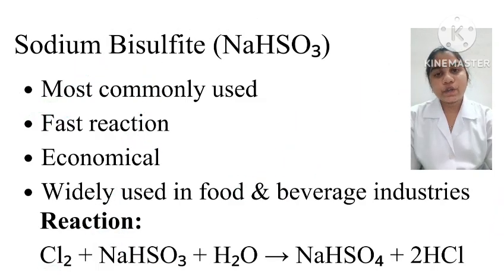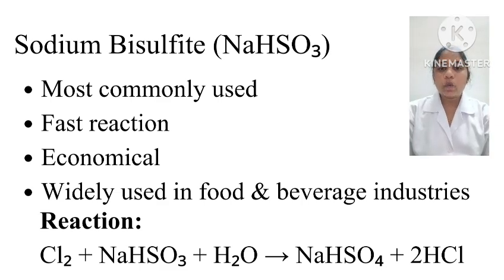Sodium bisulfite: these chemicals reduce the chlorine to chloride and form sulfate products. The process of sodium bisulfite: chlorine concentration is analyzed. A dosing pump injects the bisulfite solution into the pipeline. Next, a flash mixer ensures uniform mixing. Collect the dechlorinated water and analyze it to confirm zero residual chlorine. This process is very effective and widely used in food industries, beverage plants, and RO feed water systems.